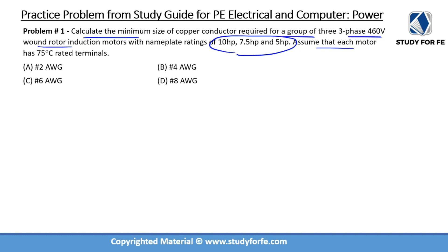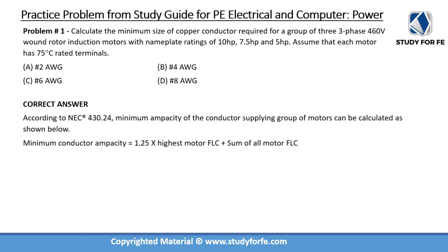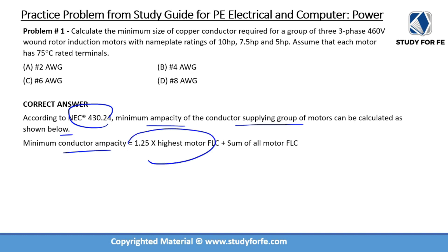We can assume that each motor has 75-degree rated terminals. According to NEC 430.24, the minimum ampacity of the conductor supplying a group of motors is equal to 125% of the highest motor FLC plus the sum of all remaining motor FLCs.